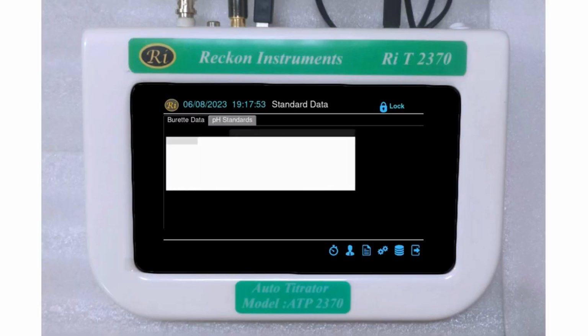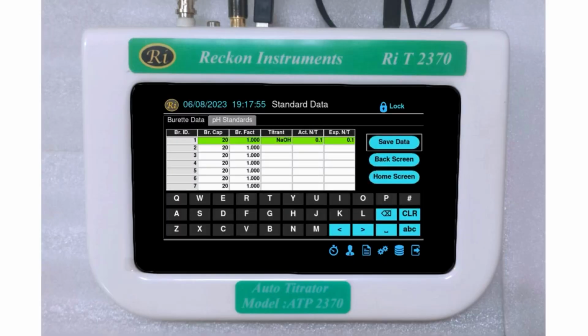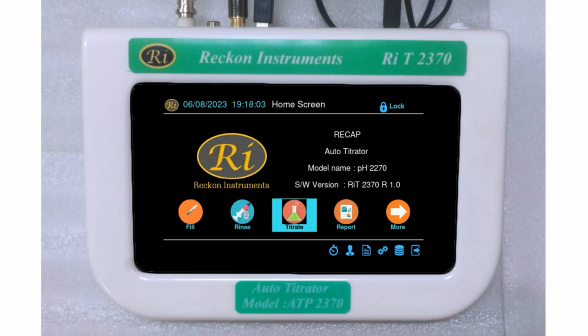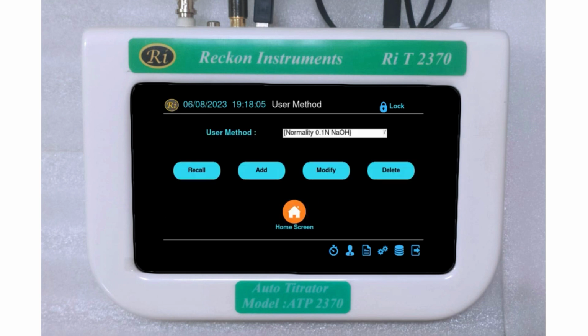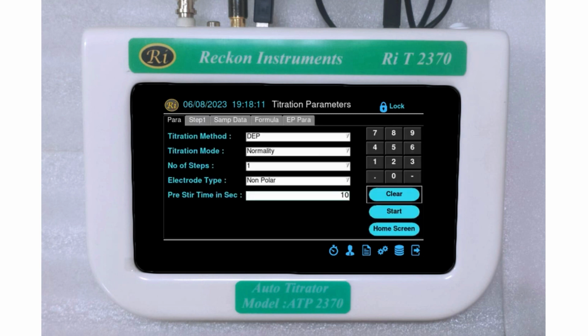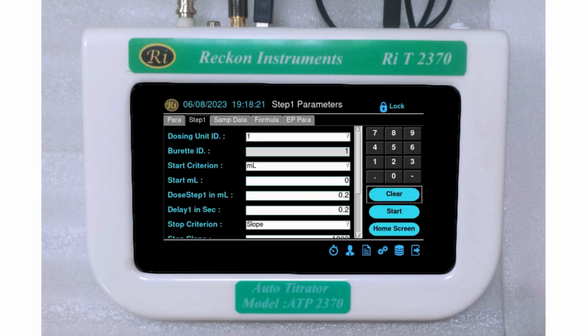Now confirm the burette and its data in the calibration standard. The connected burette row will be highlighted with green color. You can create a new user method for titration, or you can recall the saved method. To create the method, press the Add key and select the method and mode of titration, stirring time, start criteria, stop criteria, dose step, wait time, EP detection.